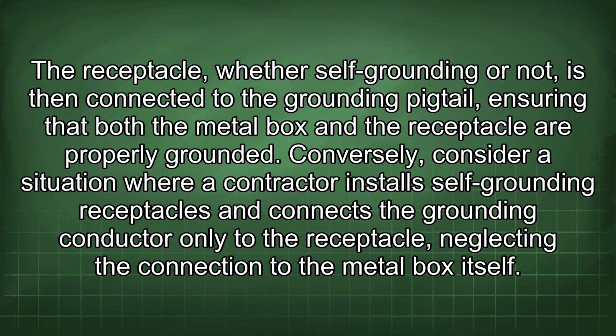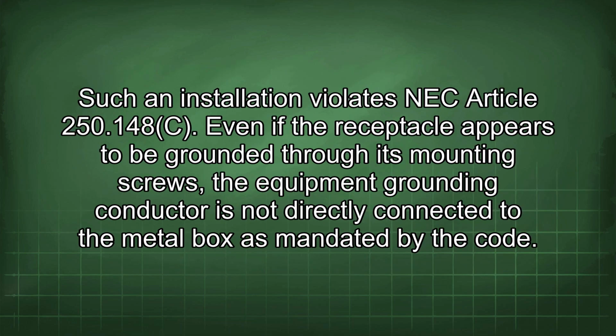Conversely, consider a situation where a contractor installs self-grounding receptacles and connects the grounding conductor only to the receptacle, neglecting the connection to the metal box itself. Such an installation violates NEC Article 250.148(C). Even if the receptacle appears to be grounded through its mounting screws, the equipment grounding conductor is not directly connected to the metal box as mandated by the code.